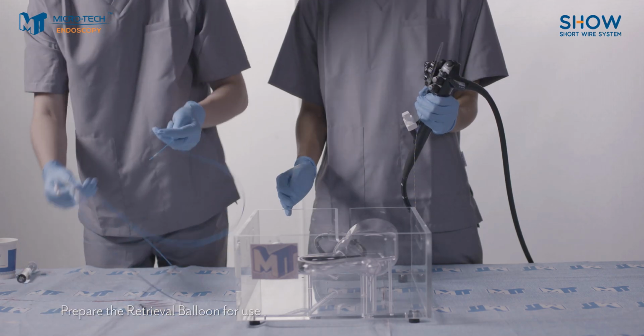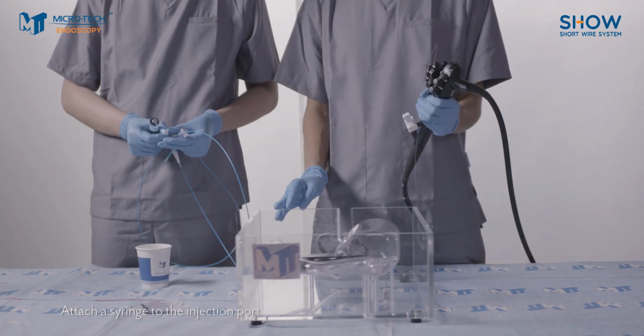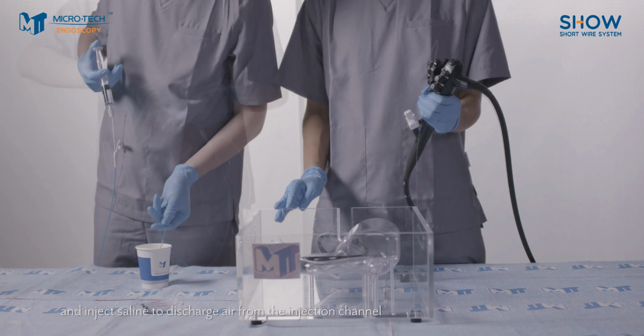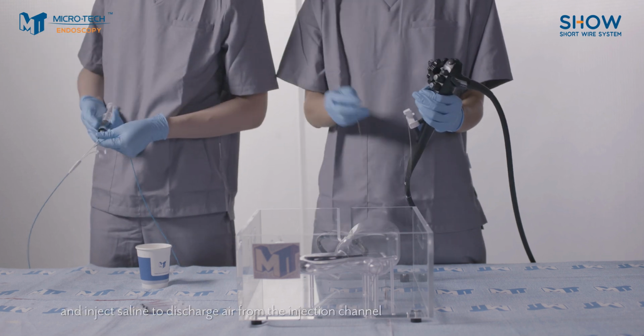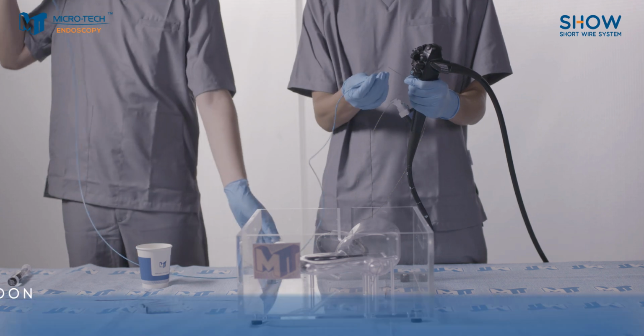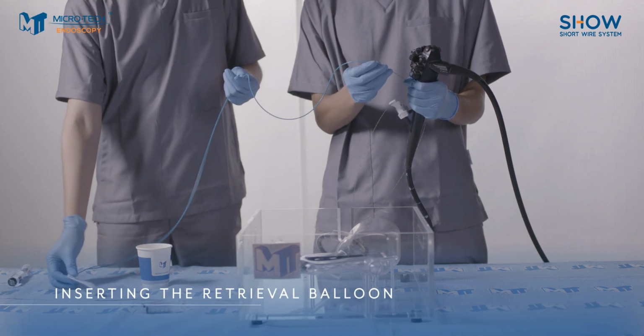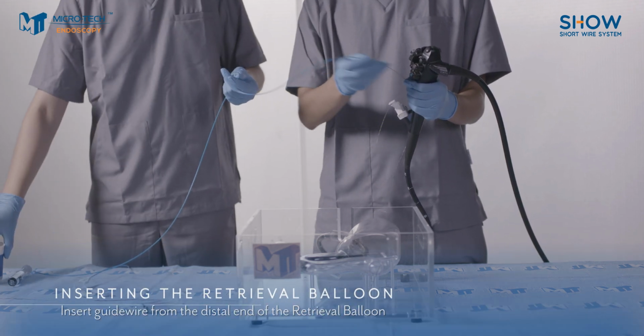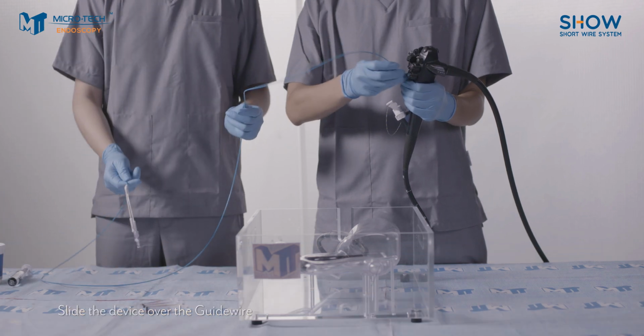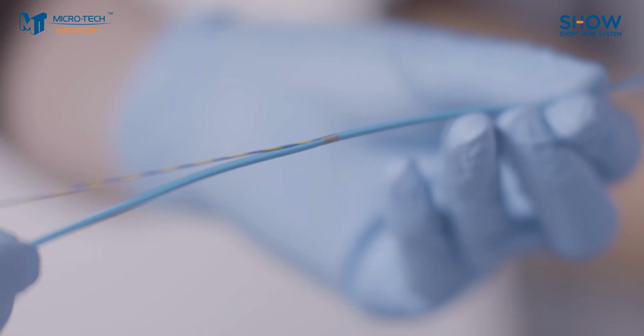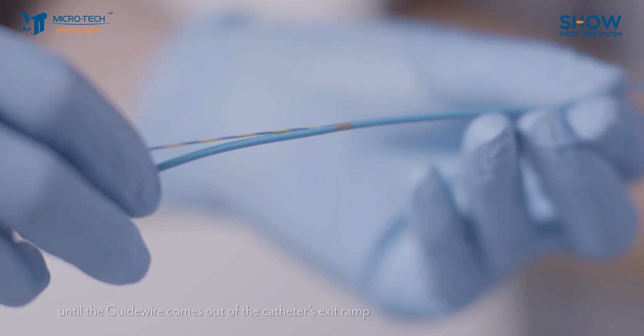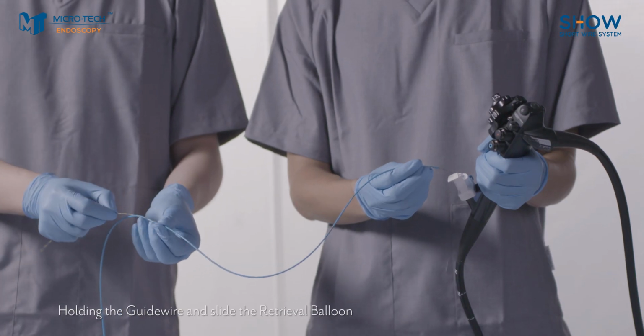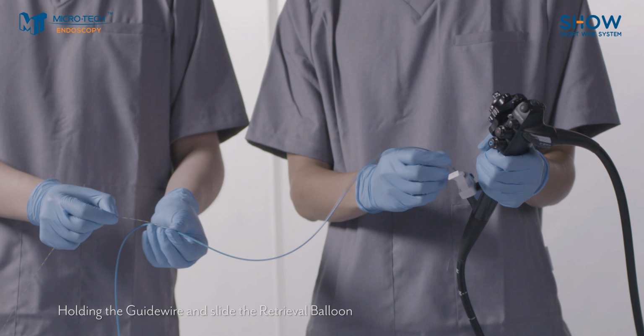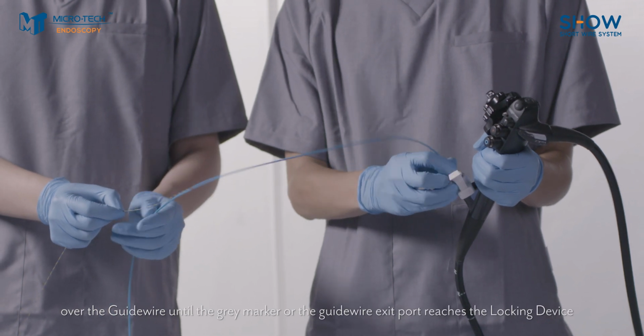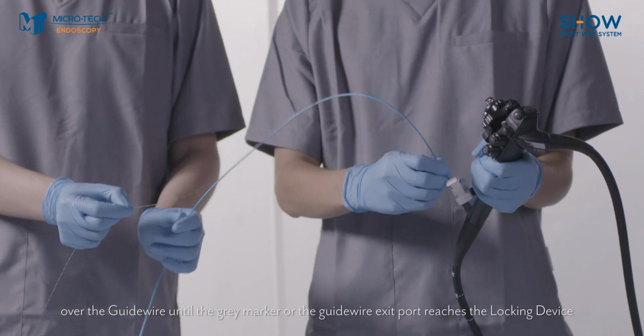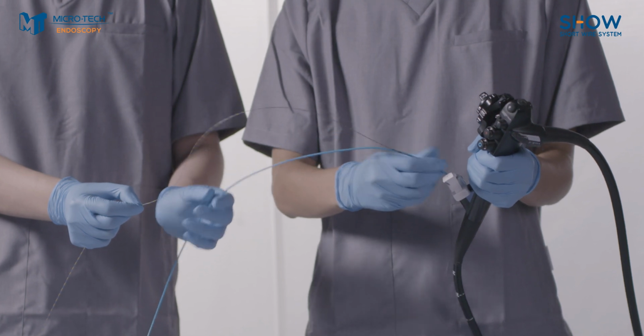Prepare the retrieval balloon for use. Attach a syringe to the injection port and inject saline to discharge air from the injection channel. Inserting the retrieval balloon. Insert the guide wire from the distal end of the retrieval balloon. Slide the device over the guide wire until the guide wire comes out of the catheter's exit ramp. Hold the guide wire and slide the retrieval balloon over the guide wire until the gray marker or the guide wire exit port reaches the locking device.